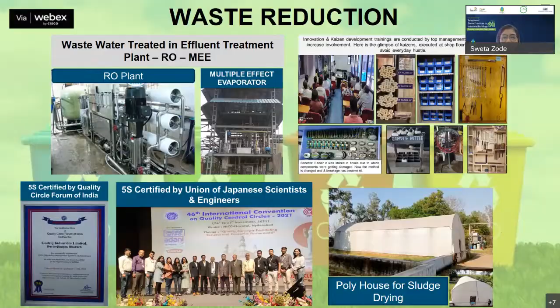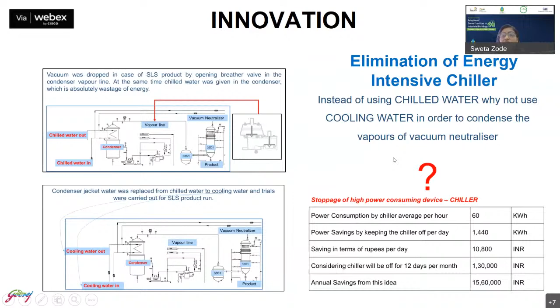Speaking about the innovation pillar, this is one example that happened inside the factory, though there are a number of innovation projects going on. This is a process intensified project where we eliminated the usage of a chiller in one process. We wanted to attain 50 to 60 mbar of vacuum inside this condenser, but realized that simple cooling water could also achieve this same vacuum. So we replaced all the chilled water with cooling water and achieved the same vacuum, leading to the elimination of the energy-intensive chiller in that process.